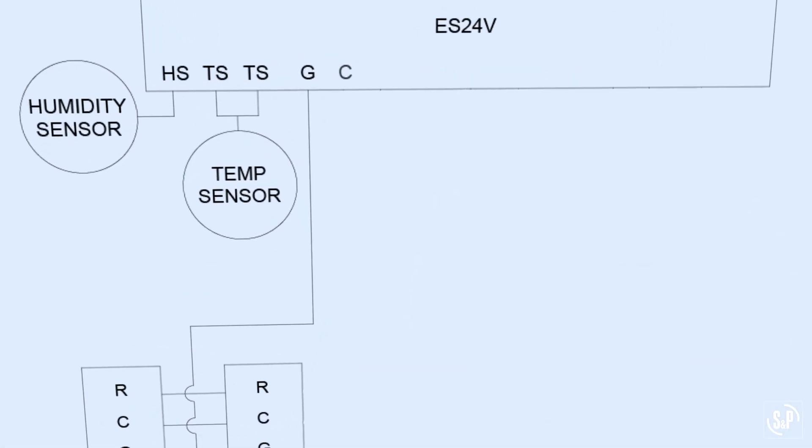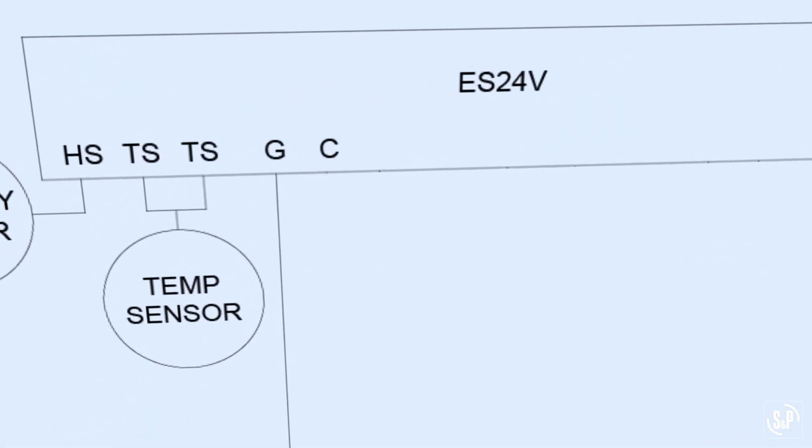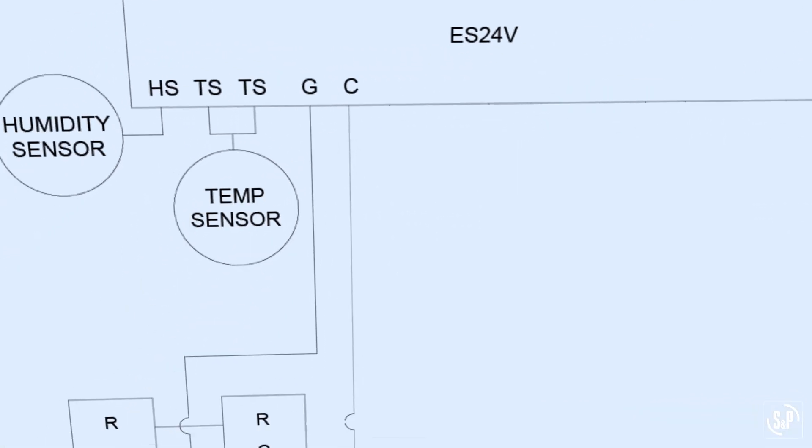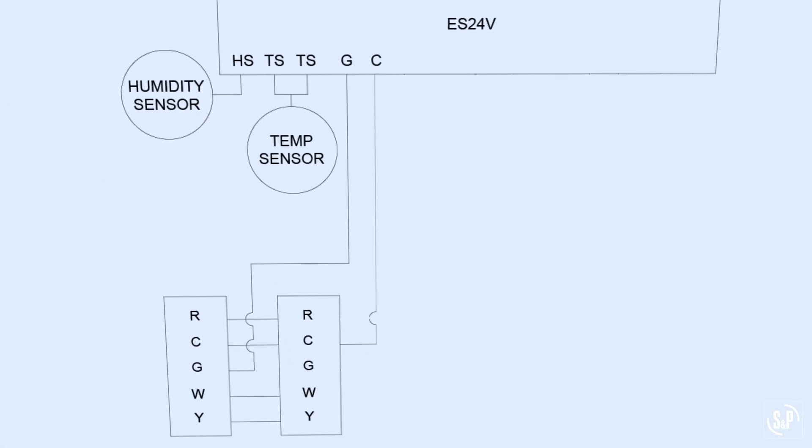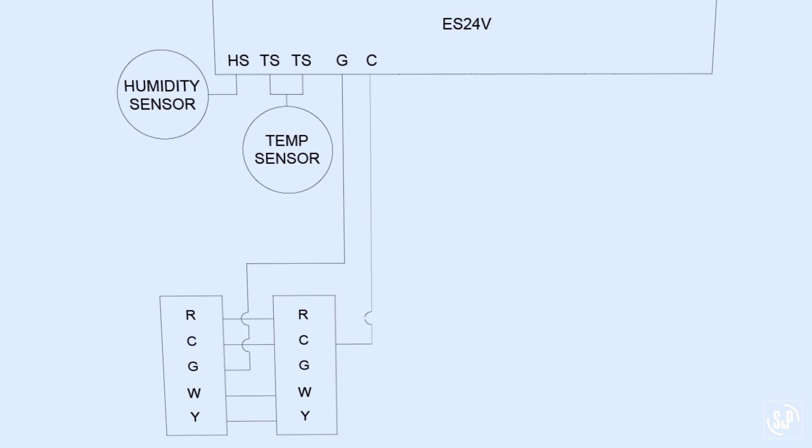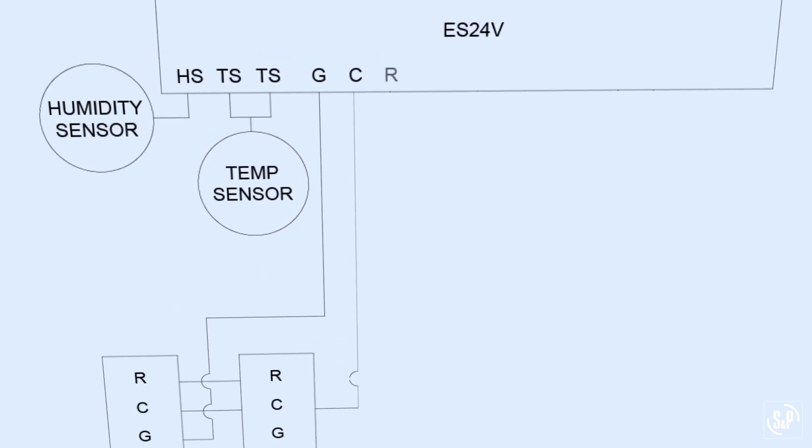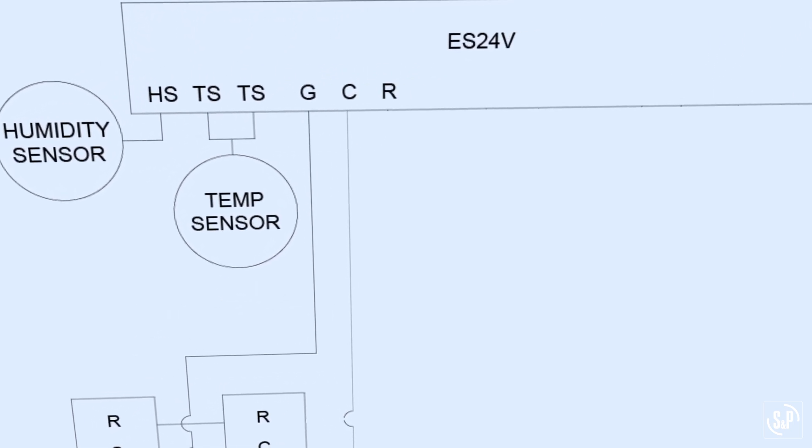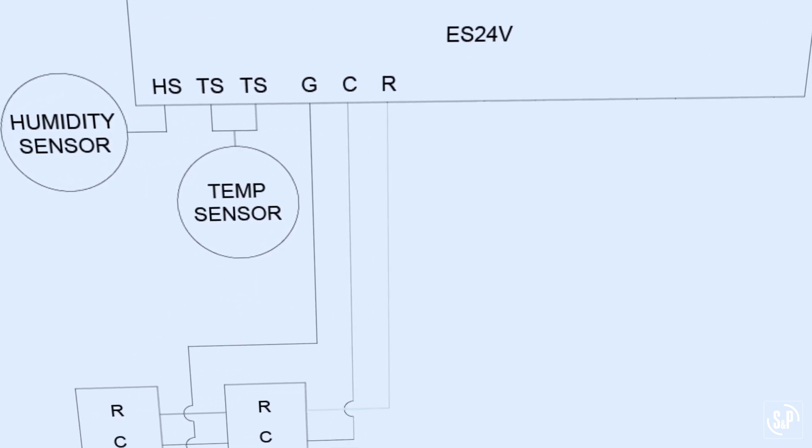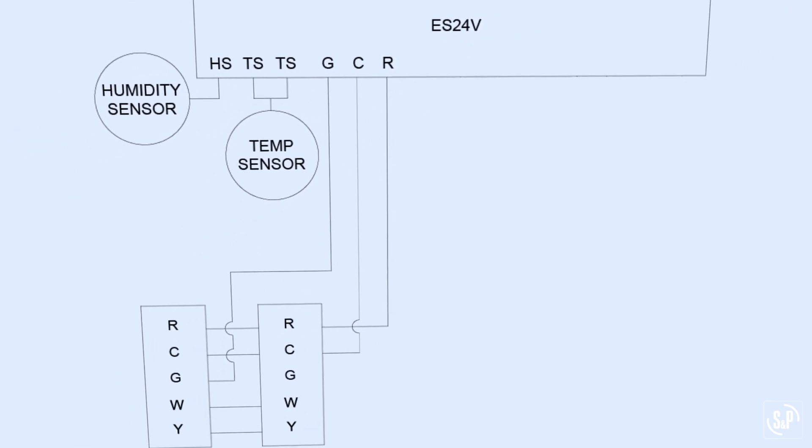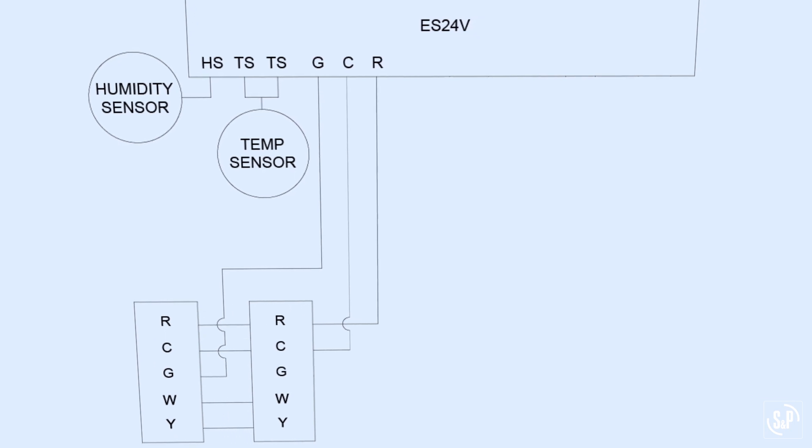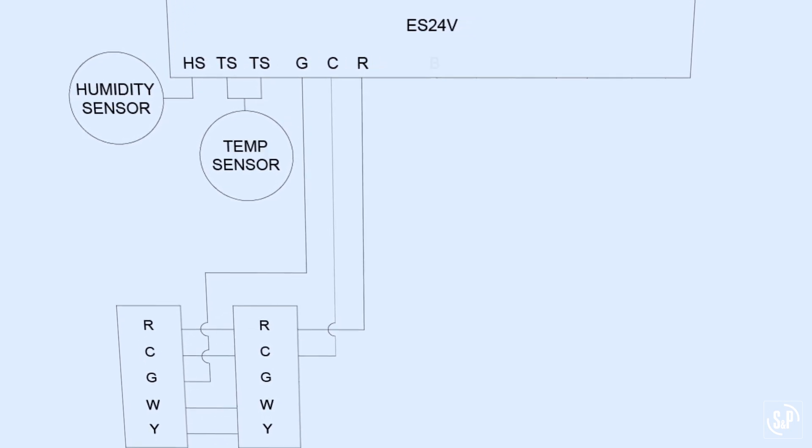The C terminal is the 24 volt AC neutral connection from the HVAC unit or auxiliary transformer. The R terminal is the 24 volt AC power or hot connection from the HVAC unit or auxiliary transformer.